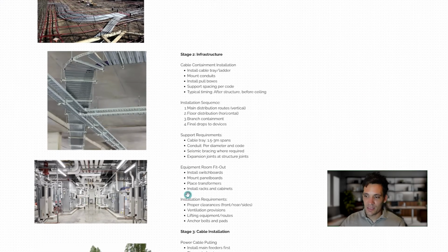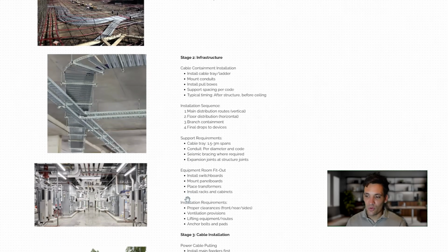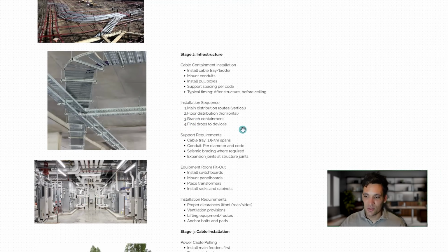It's when the building structure's up and we start to put in all the infrastructure needed for construction. So this is where we put in our cable tray and cable containment. We mount any surface mounted conduits. We install any pits or pull boxes. We put in supports, structures for lighting, these sorts of things.